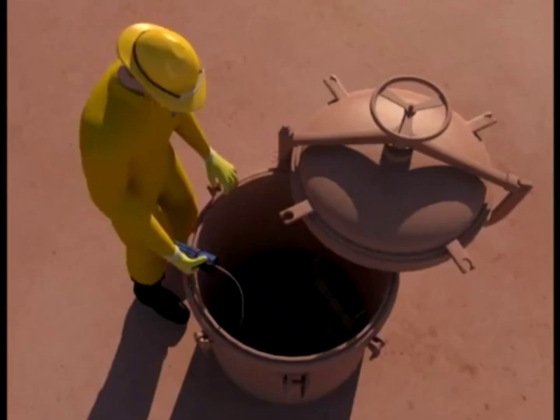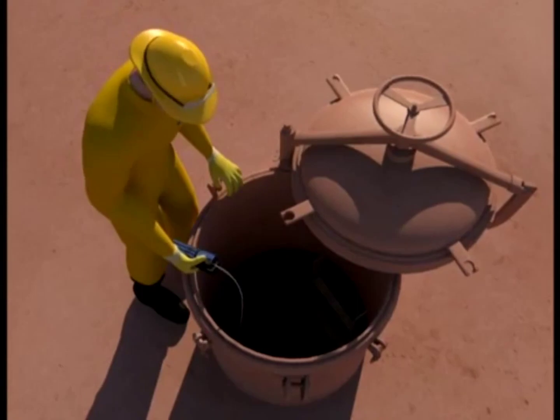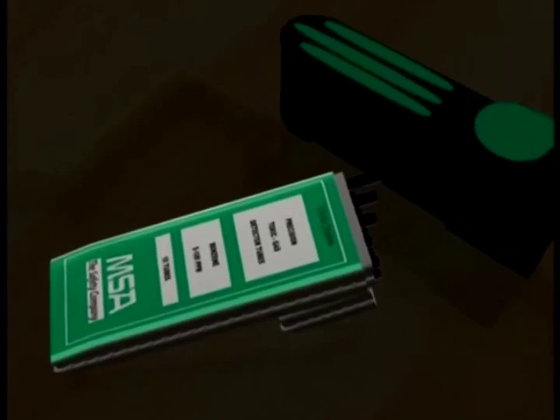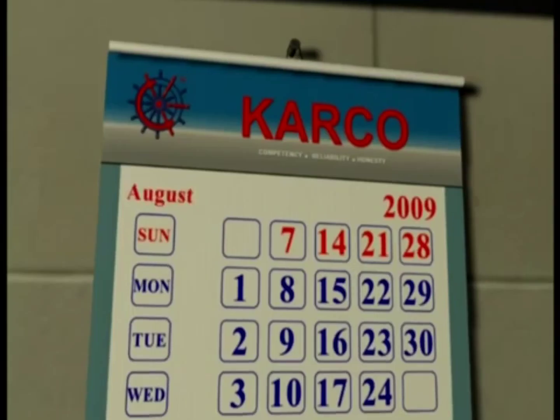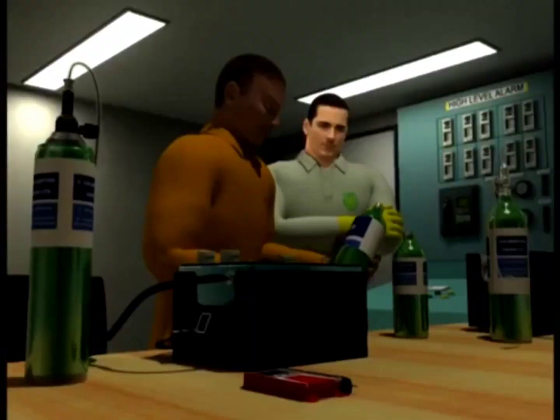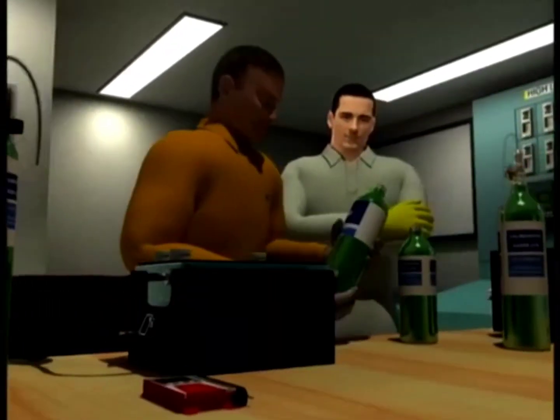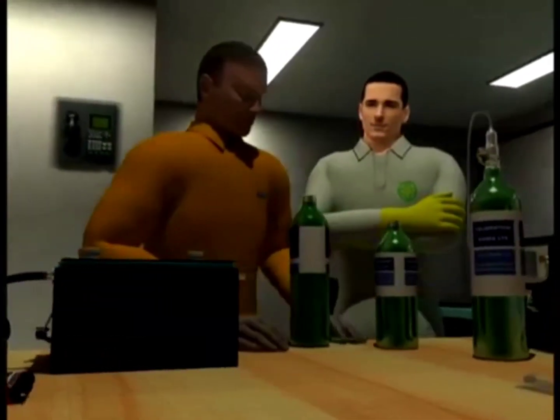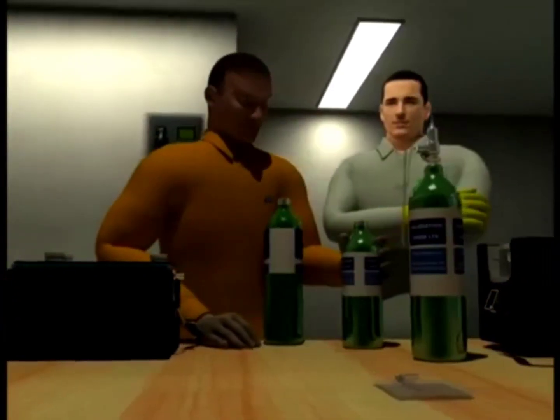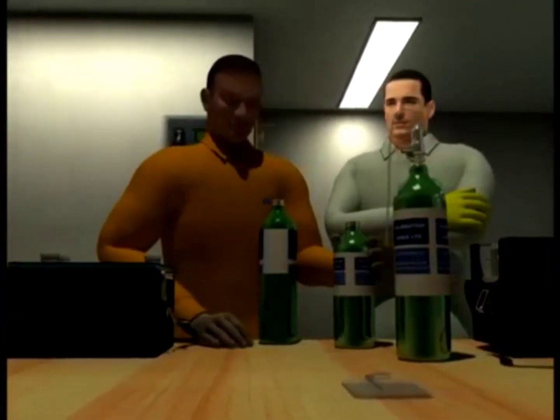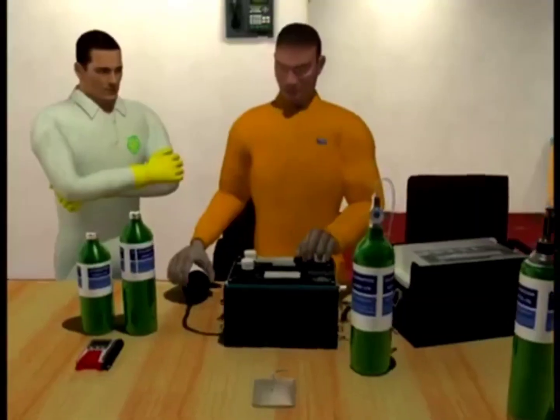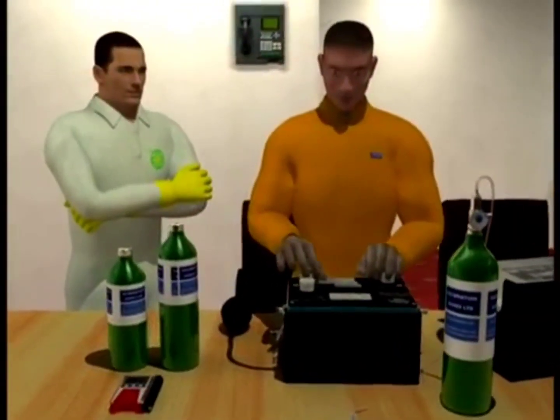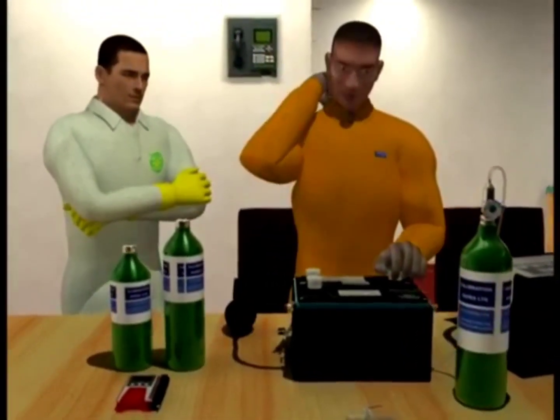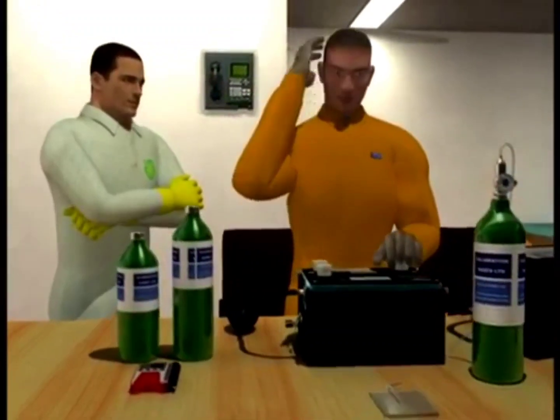The toxic gas detectors do not require any calibration to be carried out. However, the detector tubes have an expiry date and should not be used or stored beyond this date. Lack of awareness by ship staff in correct calibration procedures of portable personal gas meters is a high-risk observation by SIRE and CDI vetting inspectors.